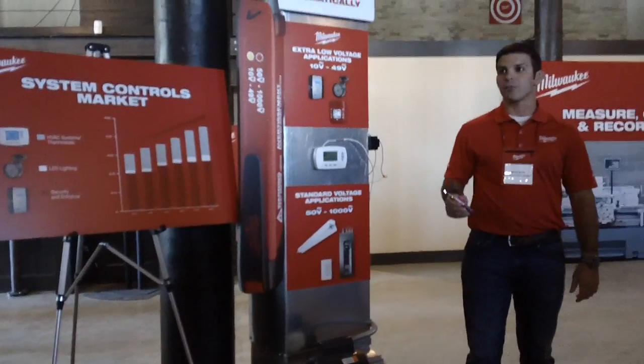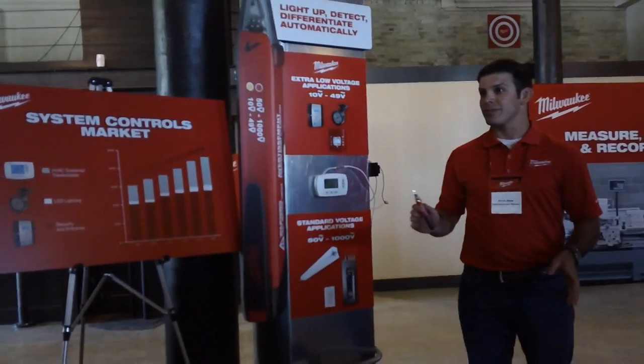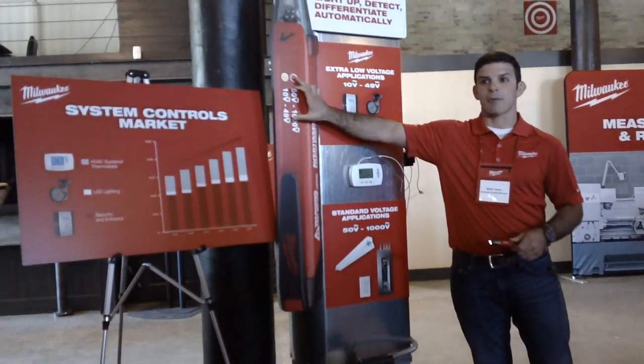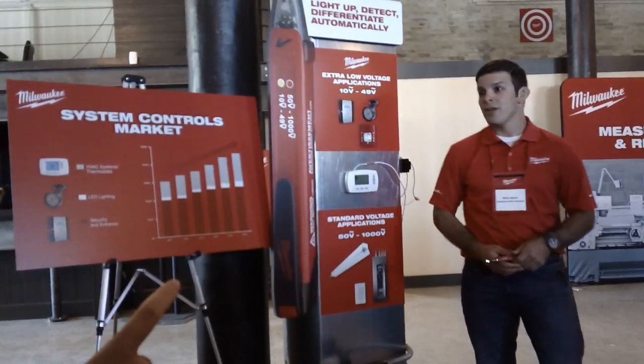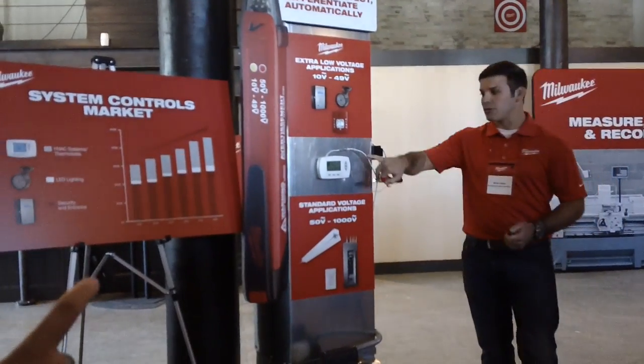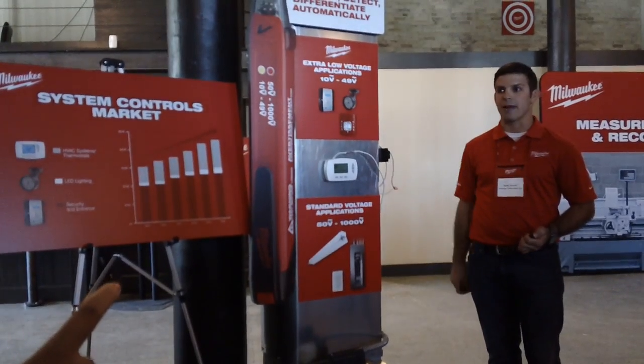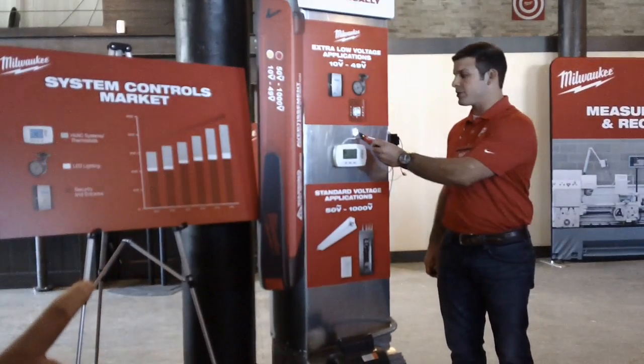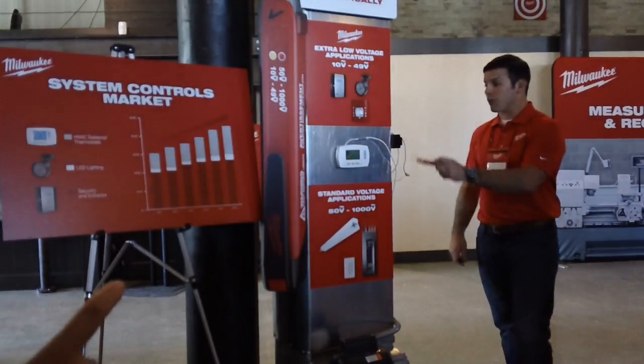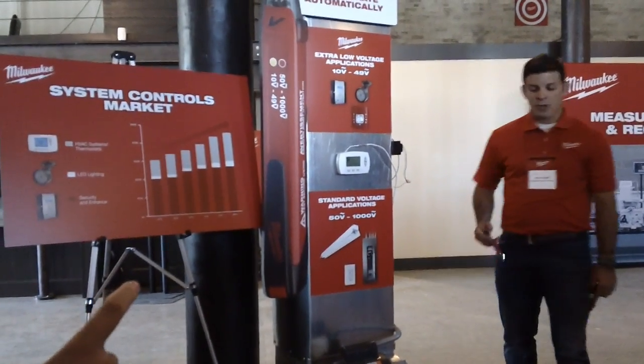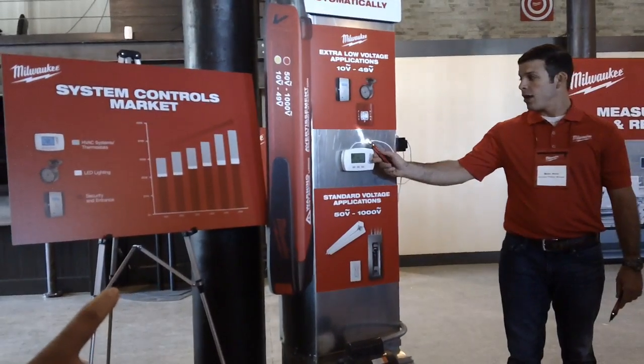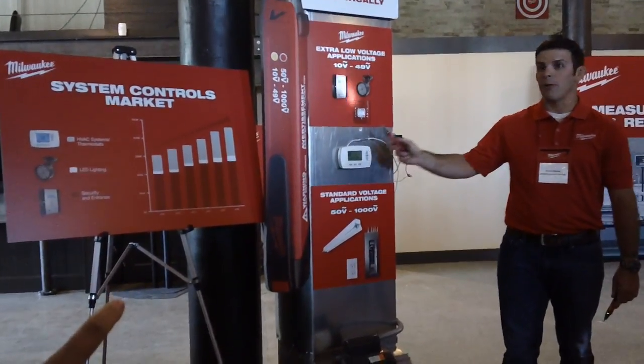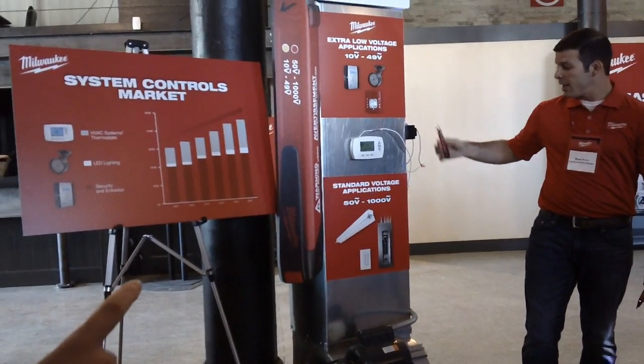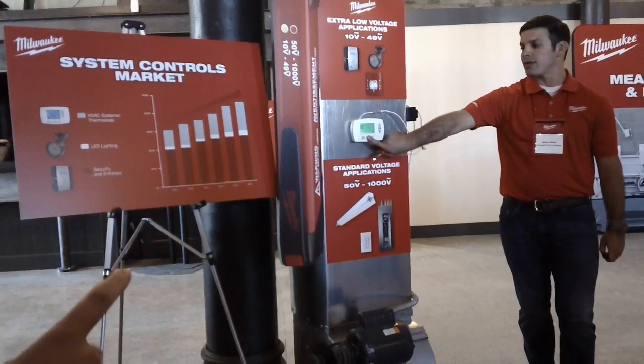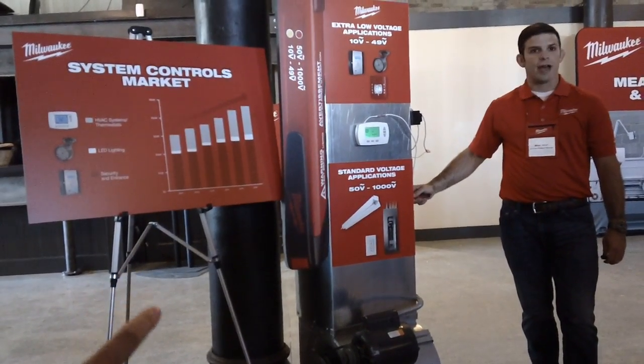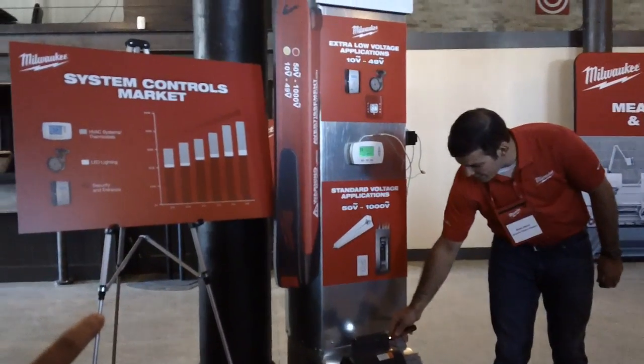So this voltage detector will detect 10 volts to 1,000 volts AC, but it not only detects that, it separates it. It differentiates the two ranges. So as I'm trying to detect, I have a 24 volt control signal running from this thermostat right now. If I try to detect it with my standard voltage detector, I'm not going to get it. If I'm going over my transformer, I see it. With my dual range voltage detector, I'll get a yellow tone and a beep. So I can tell we have voltage there, and voltage here. And then if I want to check the standard voltage, I can do that as well. So I have red here, and I'll get red down here on the motor as well.